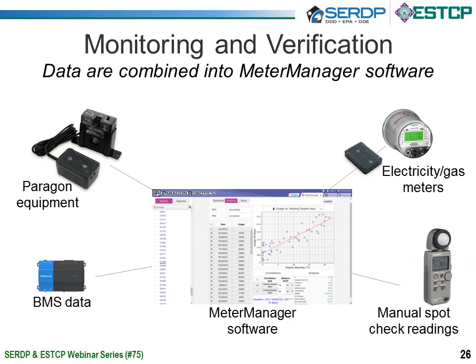And this last stage I mentioned earlier was the monitoring and verification, or M&V, stage. We have a software package called MeterManager, which is our primary interface for this M&V. What it does is take data from a wide variety of sources, ranging from BMS data, either the Paragon BMS or other BMSs installed there, capturing their data streams. It also pulls in data from our wireless sensors that are installed around there. We have interfaces for a wide variety of electricity and gas meters on the buildings themselves to pull in that data.